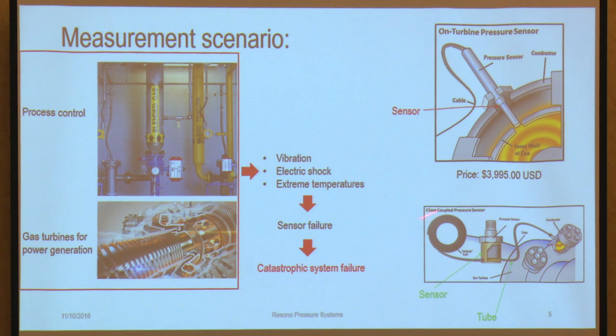If they're selling it to you for $4,000 for each one of these sensors, they're not expecting you to come back in a few years. They're actually expecting you to come back within weeks or months, because it's a very harsh environment with very high temperatures. So if this sensor fails, we'll have control failure, and when we have control failure, we can have catastrophic system failures.